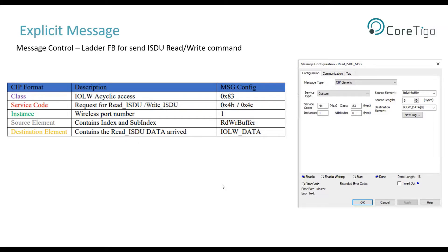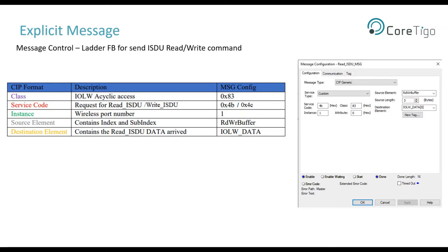In order to send ISDU commands in the Studio 5000 environment, we will use the explicit message using the message control block element. In general, the parameters of this block are: message type CIP generic, service code 4B for reading ISDU, and 4C for writing ISDU, class 83, and instance — the index of the port number at which the IO-Link device is operated.